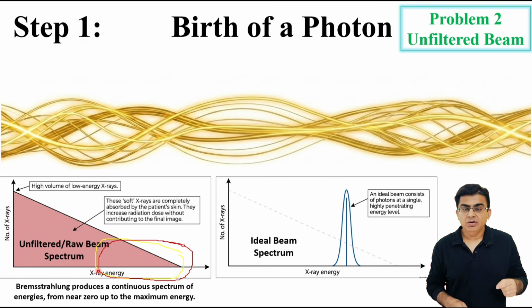If this raw beam strikes your patient, these weak photons will never reach the deep tumor. They will be entirely absorbed by the superficial tissues. They will cause severe skin toxicity without any clinical benefit. We need to create a better beam. Our machines cannot naturally produce this ideal beam, so we must artificially create it. We have found a solution for that.